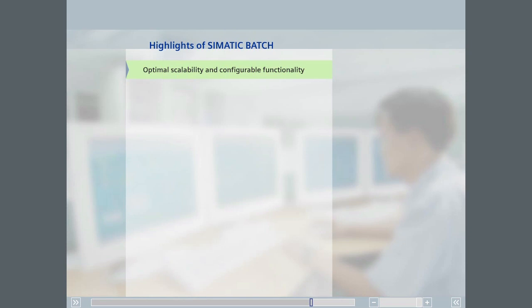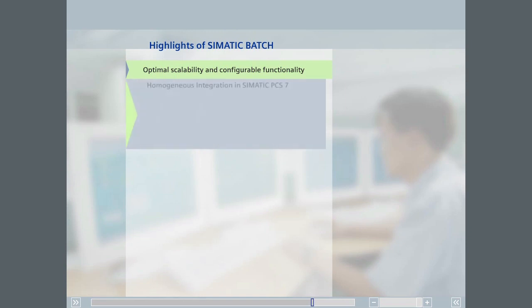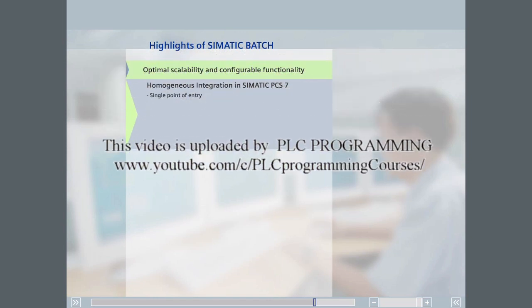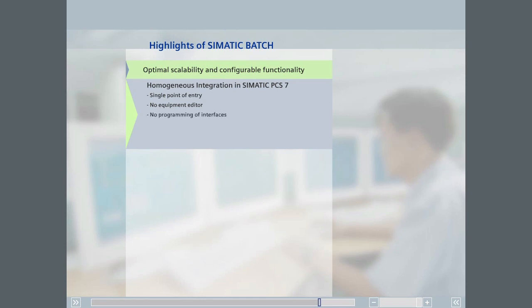To conclude this section, we would like to draw your attention to other important highlights of SIMATIC Batch. The tight integration of SIMATIC Batch in PCS 7 makes repeated entry of configuration data during engineering unnecessary. The process model configured for use in the automation system is also used in SIMATIC Batch; therefore, no additional equipment editor — as needed with some other batch systems — is required. It is also not necessary to program or configure interfaces between the batch system and the automation system.